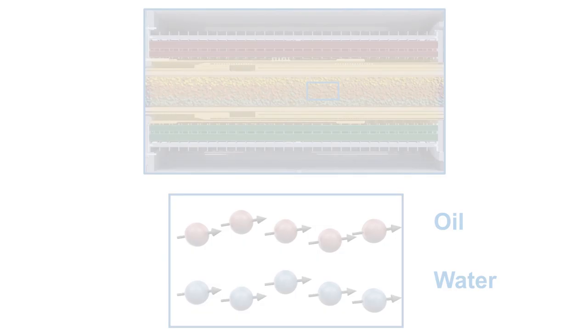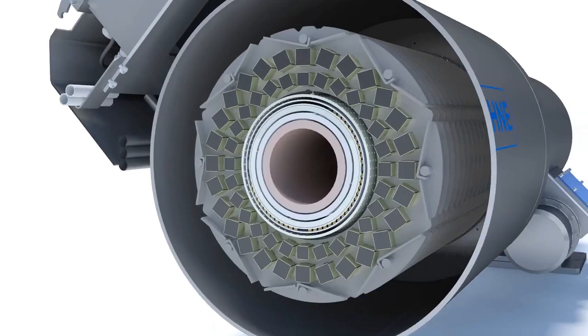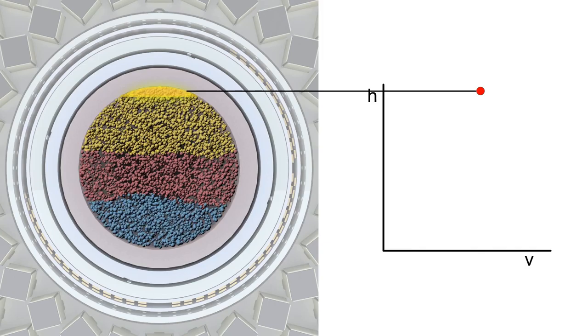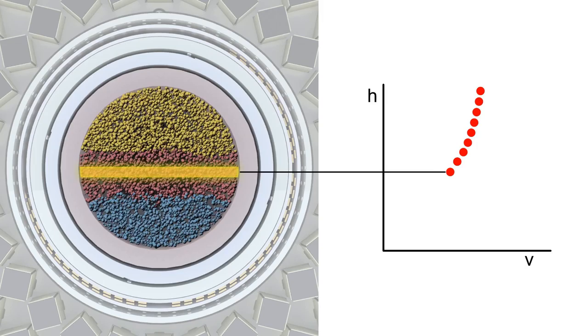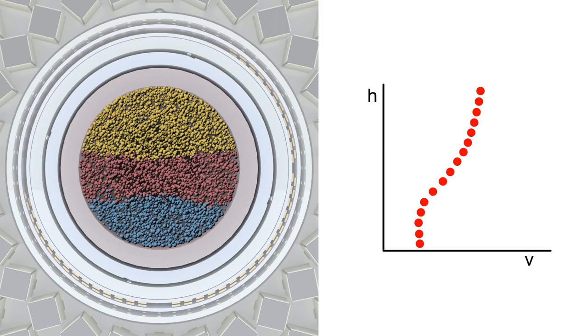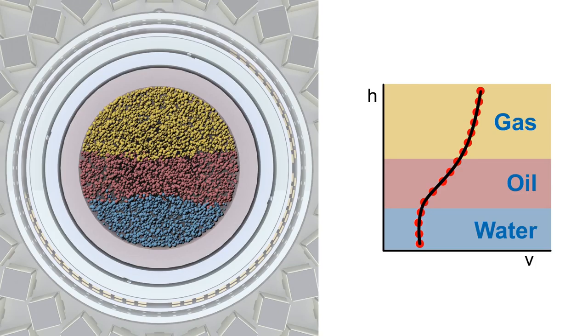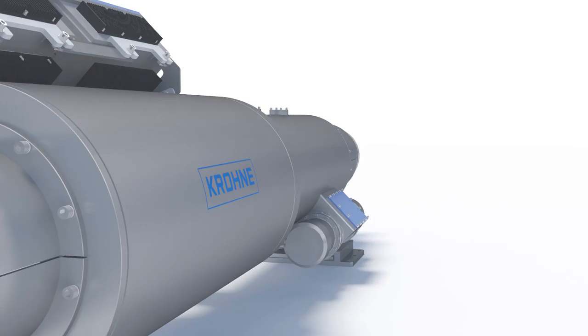Additional information on the gas velocity is obtained by exciting a gradient coil. The coil induces a magnetic field which is strong in the top of the pipe and weaker at the bottom. Tuning the frequency of the radio frequency pulses to the magnetic field strength allows performing measurements in selected slices in the pipe. From this information, the gas flow rate can be determined.